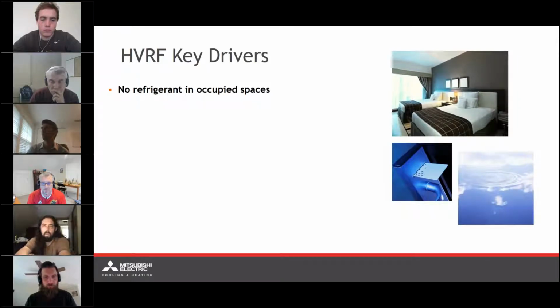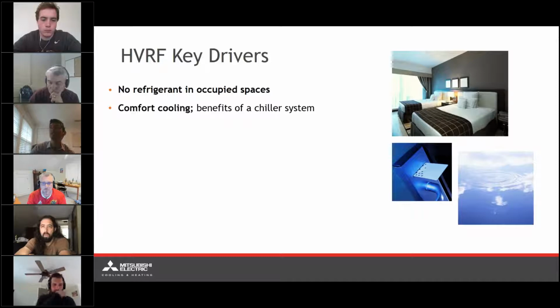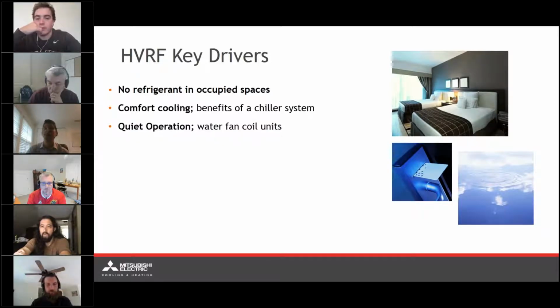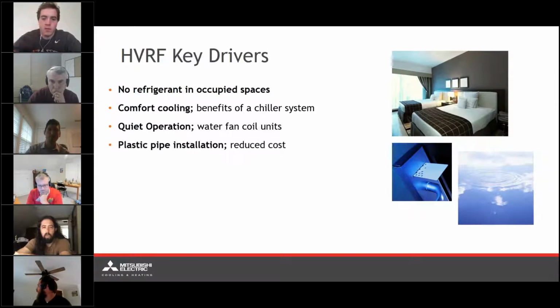In any of the spaces, we're just running water through the spaces. We're going to have the benefits of a chiller system, very, very comfortable cooling benefits. Super quiet operation. I know VRF is known for its super quiet operation, but now we're removing even the sound of the clicking of the valve. You may get that if you're super particular and want the most quiet system possible, and maybe the clicking of the valve is a bit too much for you. This is even more quiet. So we're going to be getting similar decibel levels to water fan coil units.